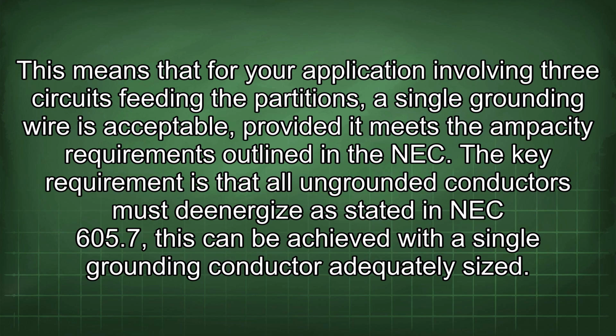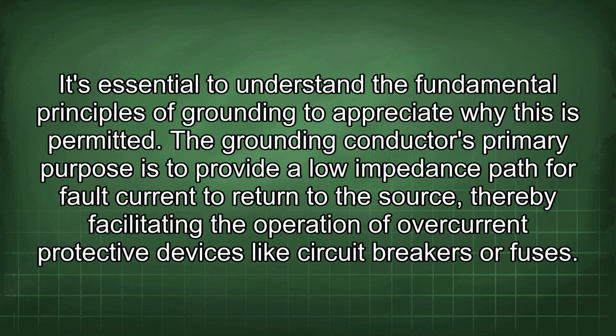The key requirement is that all ungrounded conductors must deenergize as stated in NEC 605.7. This can be achieved with a single grounding conductor adequately sized. It's essential to understand the fundamental principles of grounding to appreciate why this is permitted. The grounding conductor's primary purpose is to provide a low impedance path for fault current to return to the source, thereby facilitating the operation of overcurrent protective devices like circuit breakers or fuses.